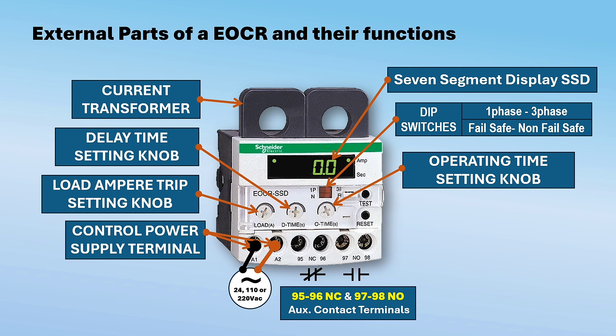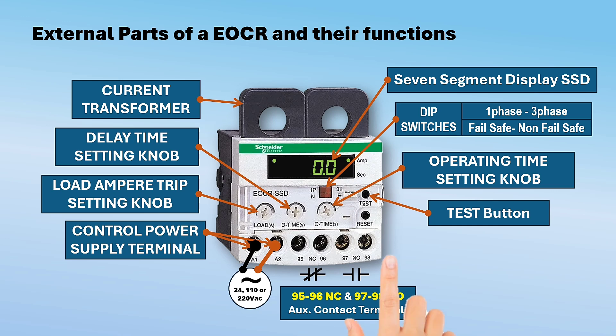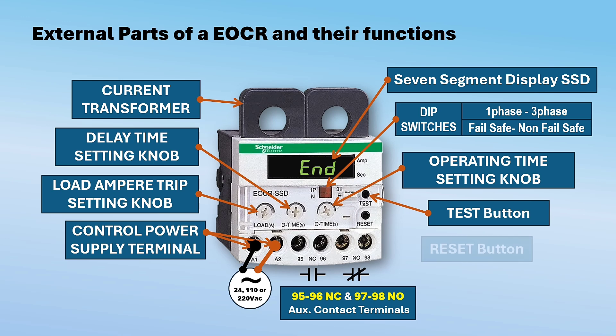Test button — it is a force trip button used to check the EOCR trip function and auxiliary contact status. The test function is only possible when the motor is in stop status and not possible while the motor is running. Reset button — depressing the reset button or interrupting the power supply to the EOCR returns the relay to normal pre-start condition.